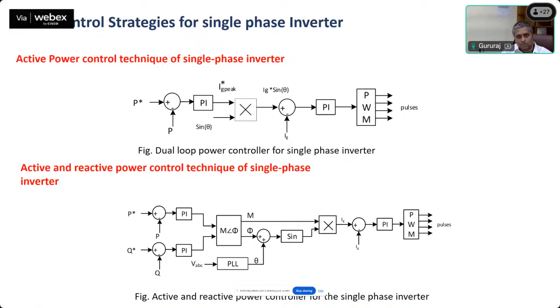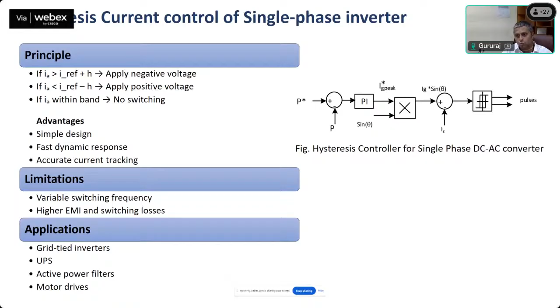More or less it looks the same. Hysteresis current control is also one of the widely researched controllers, because unlike the PI controller which operates on a DC platform, so you don't have to convert from ABC to DQ. You can directly use this hysteresis current controller, and then the AC signal can be compared directly, and the switching pulses can be generated. But the only challenge with this hysteresis controller is the filter size. Choosing the proper filter size would be challenging because of the variable switching frequency. Or the other option could be to go for a variable bandwidth, and the switching frequency can be fixed. And if the switching frequency can be fixed, then that is helpful for us to choose the filter size.